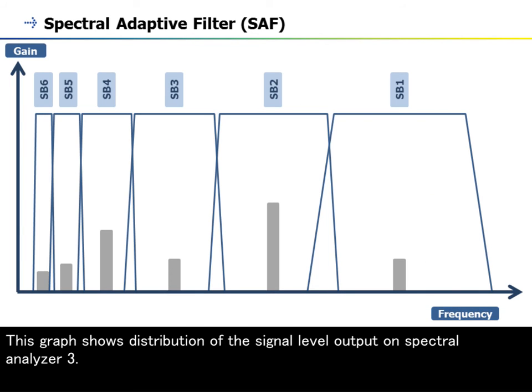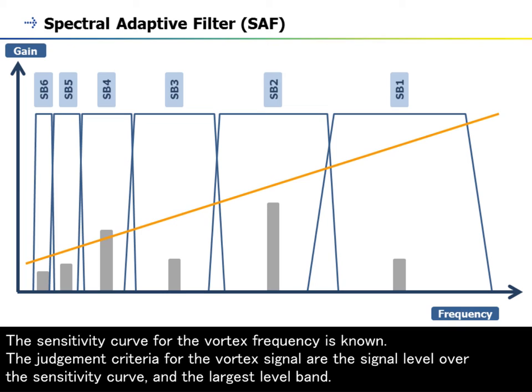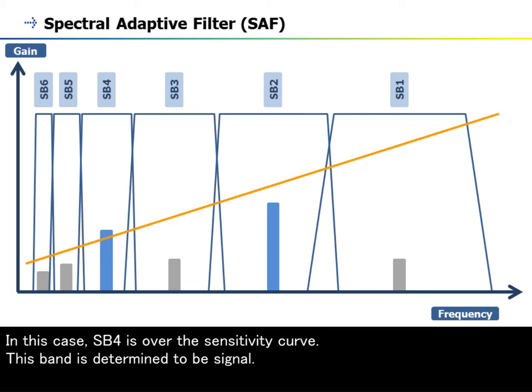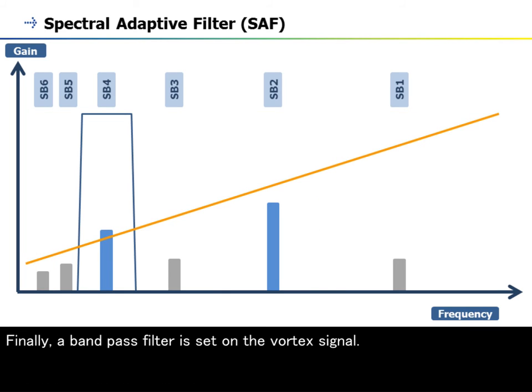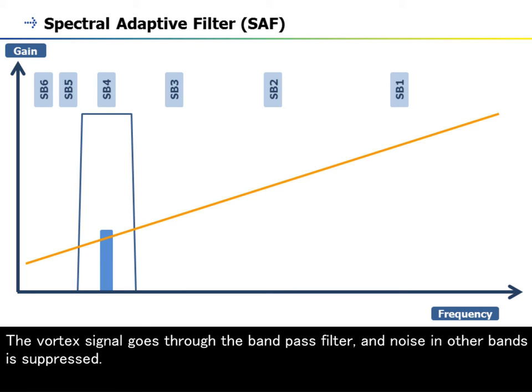This graph shows the distribution of the signal level output on spectral analyzer 3. The sensitivity curve for the vortex frequency is known. The judgment criteria for the vortex signal are the signal level over the sensitivity curve and the largest level band. In this case, Sb4 is over the sensitivity curve — this band is determined to be signal. Sb2 is larger than Sb4, but its signal level is lower than the sensitivity curve, so it is determined to be noise. Finally, a bandpass filter is set on the vortex signal. The vortex signal goes through the bandpass filter, and noise in other bands is suppressed.